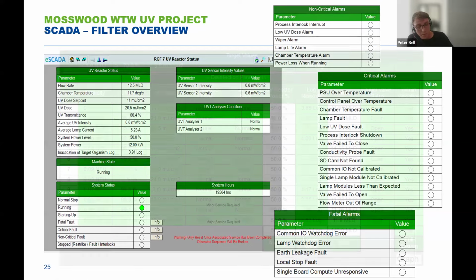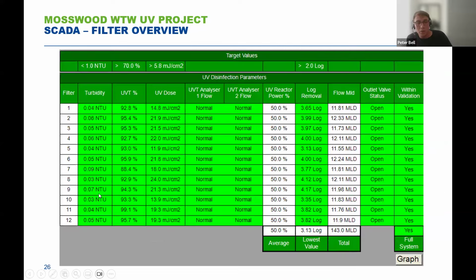Next slide, please, Andy. Because of the level of information available, what we then did was break that down to the absolutely critical points to help the operators understand the performance of the UV. So just to give you a little bit of an overview, the first column here is turbidity. That is showing what the turbidity of the filter is coming at. Andy touched a little bit on this earlier, but we need the filters to be presenting less than 1 NTU turbidity so that disinfection can take place appropriately.